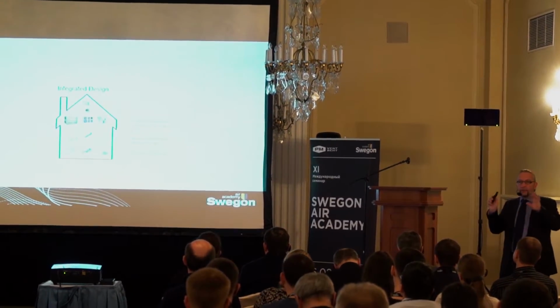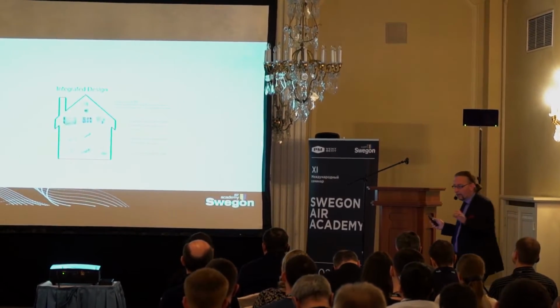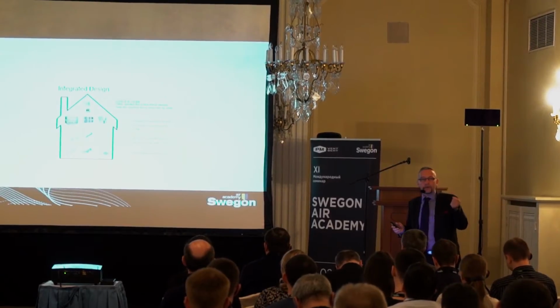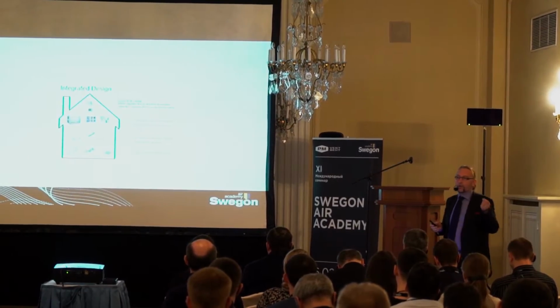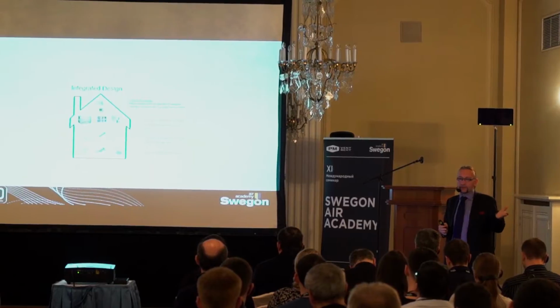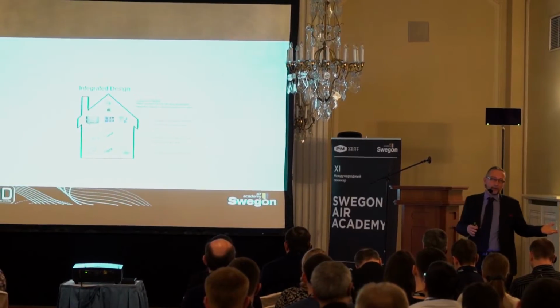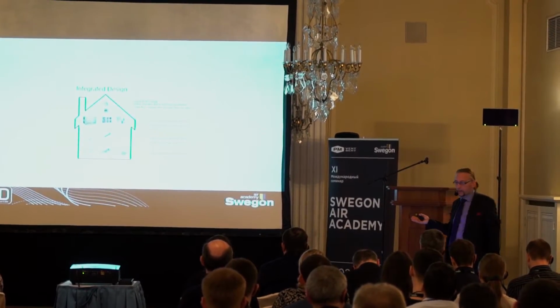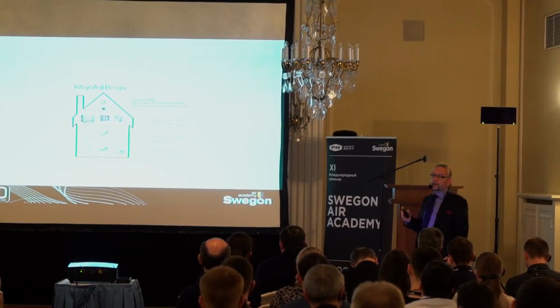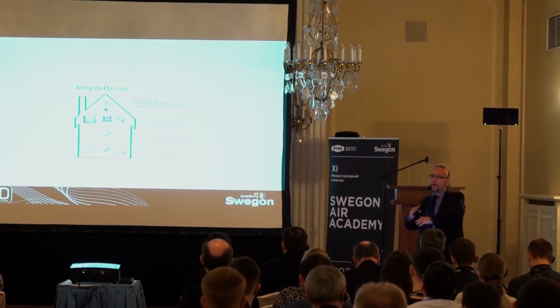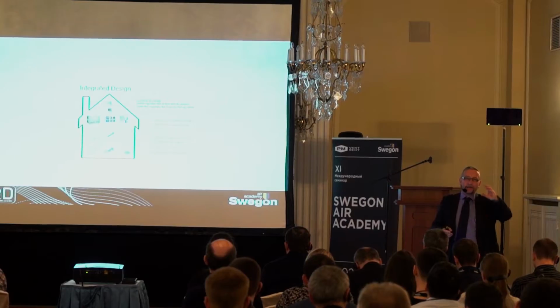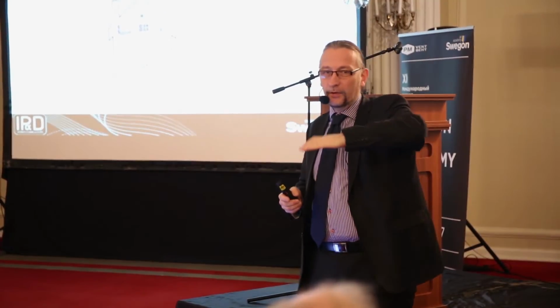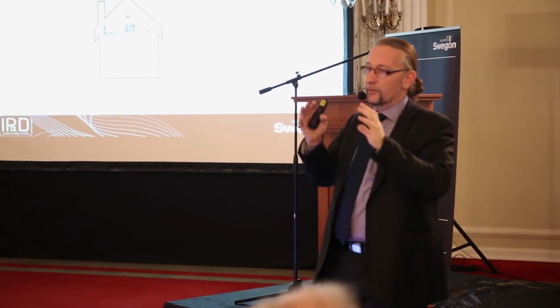If you only remember one thing from this seminar, the rule of thumb when you control media is: always work with as low pressures as possible, both on the air side and the water side. So you'd rather regulate the air volume by regulating the fan than by regulating a damper, because regulating a damper creates pressure. By slowing down the fan instead, you save energy.